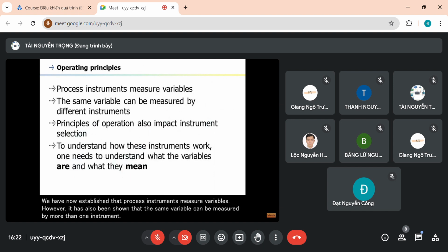We have now established that process instruments measure variables. However, it has also been shown that the same variable can be measured by more than one instrument. Instruments differ in how they measure variables. A Coriolis flow meter uses Coriolis acceleration, whereas a magnetic flow meter uses Faraday's law, but they both measure flow. How an instrument works, its operating principle, also influences whether it can be selected for an application. To understand instruments' operating principles, you need to know what variables are measured and how these variables interact with one another. For example, the first step in selecting a temperature measuring instrument is to understand what temperature is and what it means.